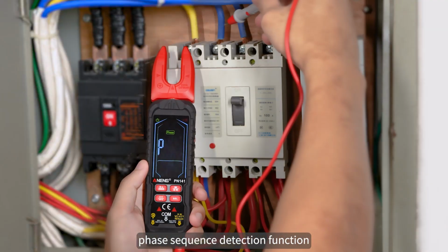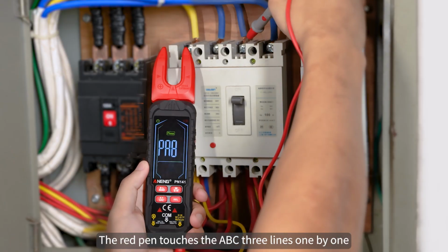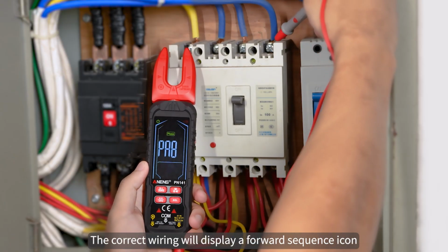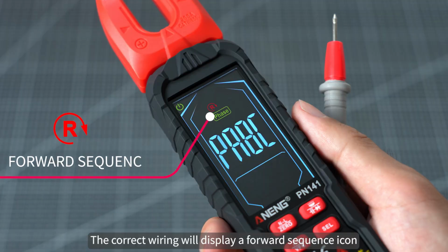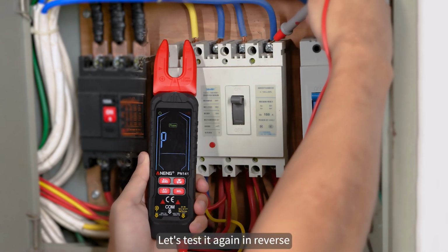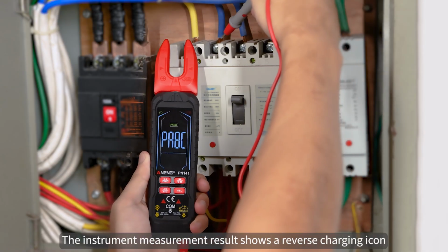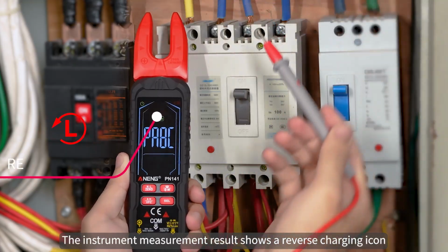Phase sequence detection function: the red pen touches the ABC 3 lines one by one. The correct wiring will display a forward sequence icon. Let's test it again in reverse - when there is a wiring error, the instrument measurement result shows a reverse phase icon.